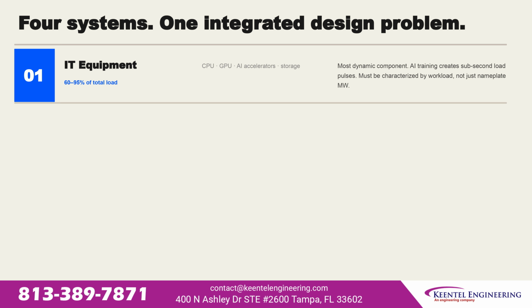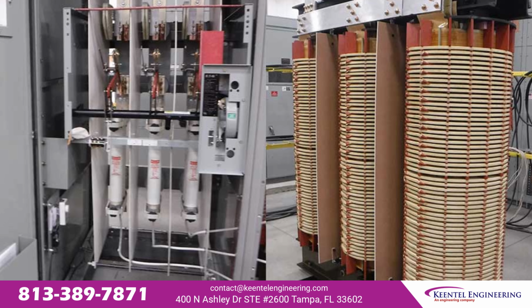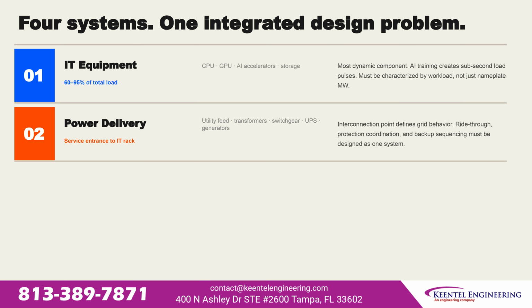NERC frames data center electrical architecture as 4 systems, and all 4 must be designed as one integrated problem. 1. IT equipment, 60 to 95% of total load: CPUs, GPUs, AI accelerators, storage. The most dynamic component. AI training creates sub-second load pulses. It must be characterized by workload, not nameplate megawatts. 2. Power delivery, service entrance to IT rack: utility feed, transformers, switchgear, UPS, generators. The interconnection point defines grid behavior. Ride-through, protection coordination, and backup sequencing must be designed together.